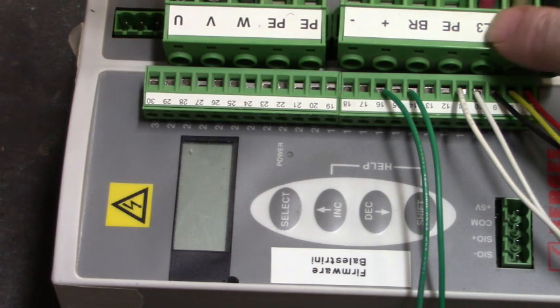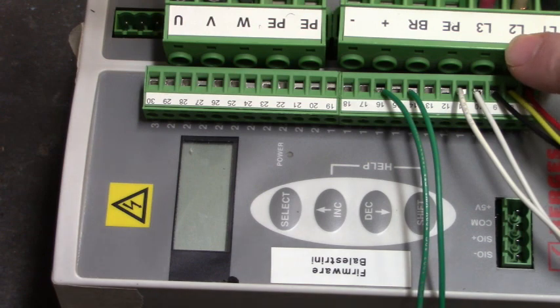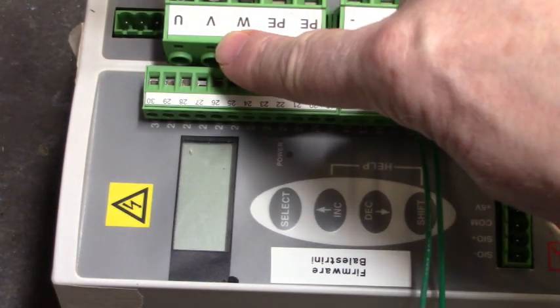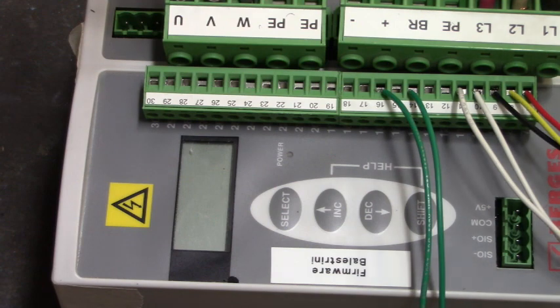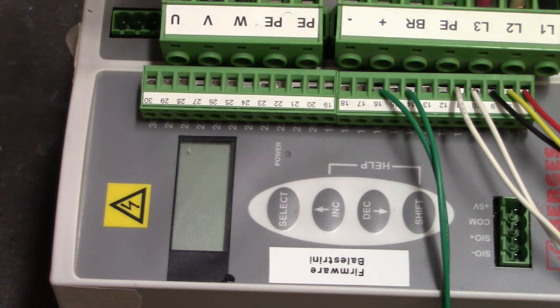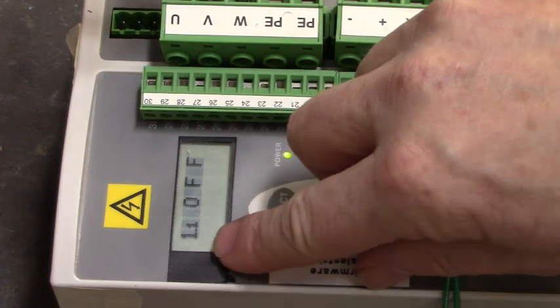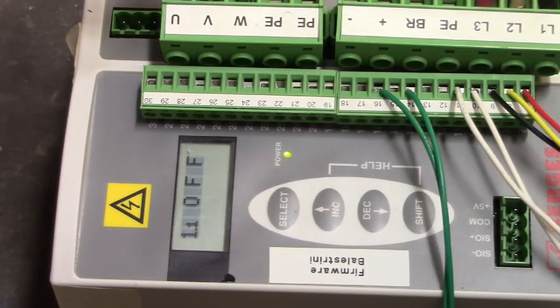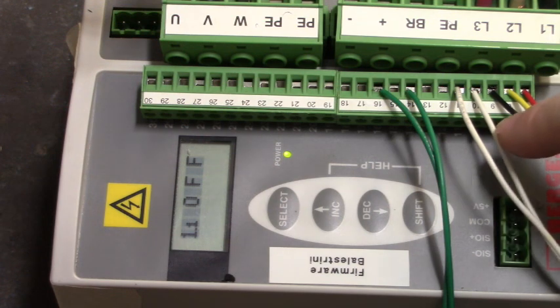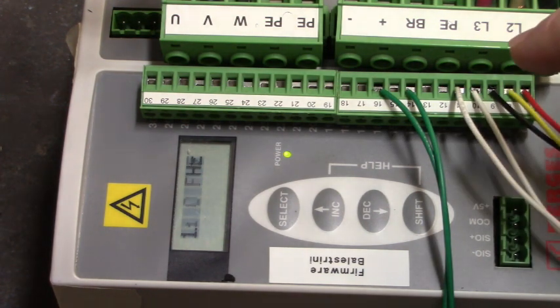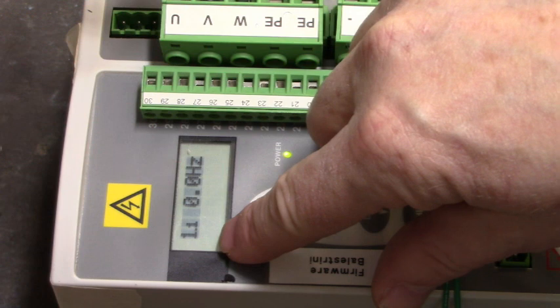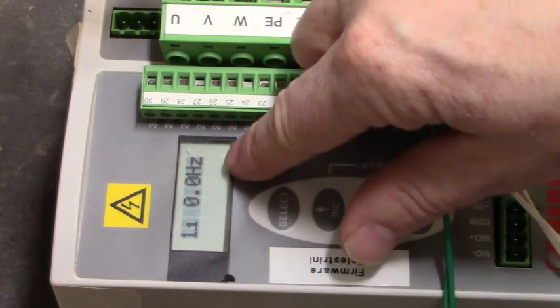L1, L2, and L3 up here are the line in, and U, V, and W are the motor outputs to the spindle motor. Okay, we're going to apply 380 volts, three phase to L1, L2, and L3. And the drive powers up to 1.1 off. I'm going to close the switch at terminals 10 and 11. And now the drive displays 1.1 0.0 hertz.